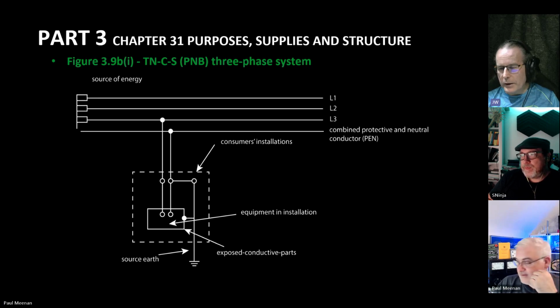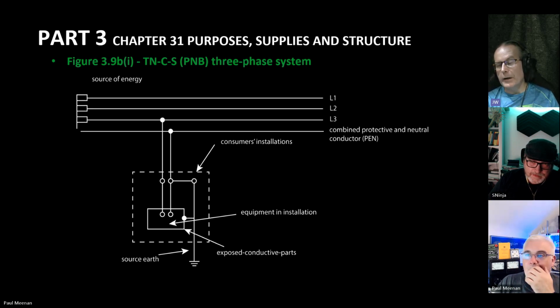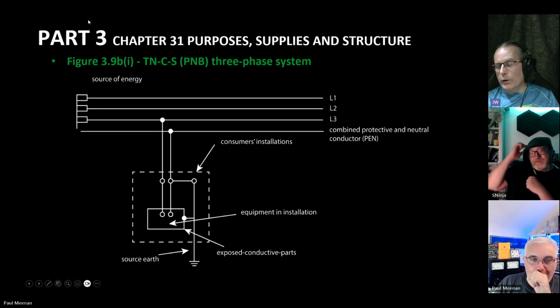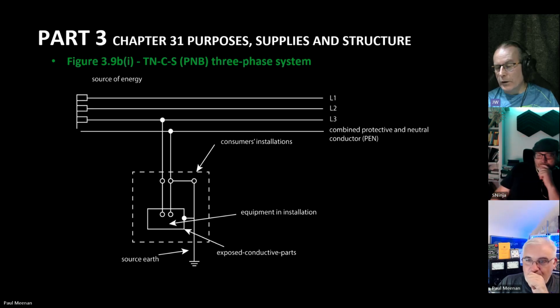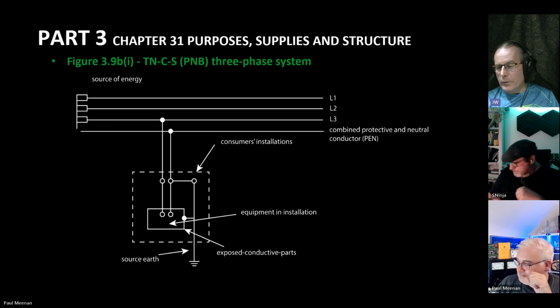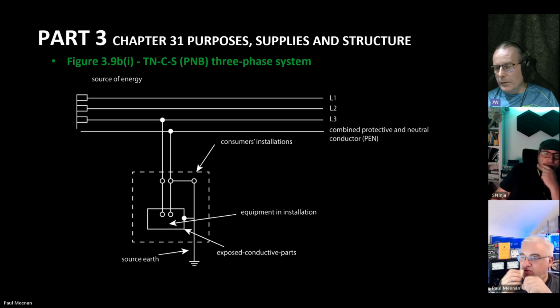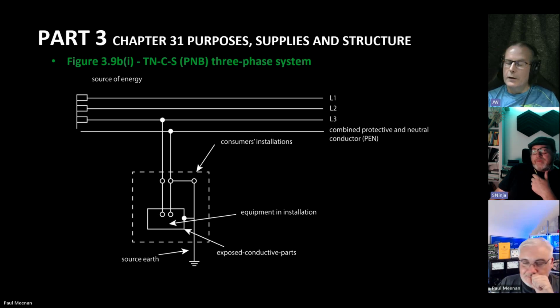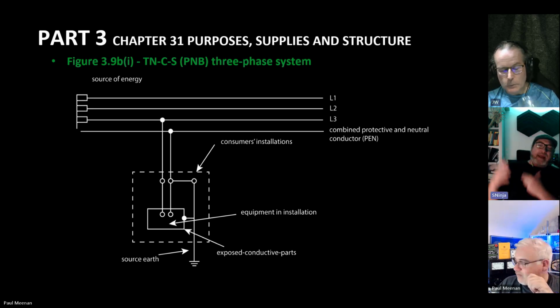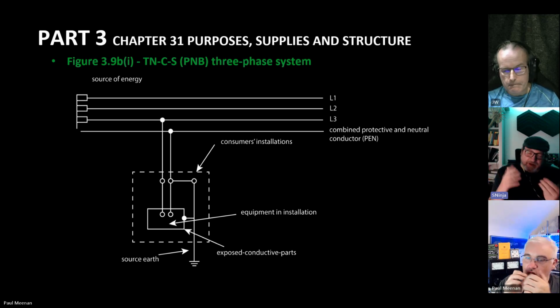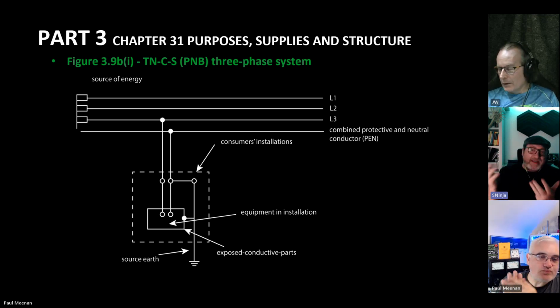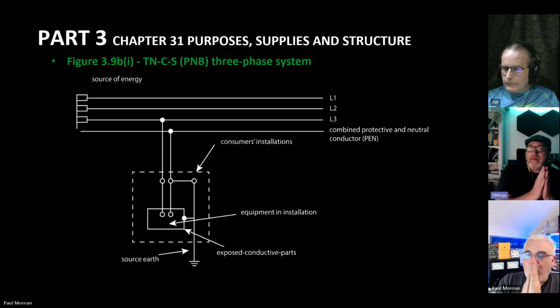The key difference with these on the diagram is that it's still TNCS. The difference between PNB and PME is that with PNB there's only one connection between the neutral and earth, and that's in the dotted box there, and that's also where the electrode is. Whereas with PME, you've got a link there, but there's also going to be other links in the actual network itself, and other electrodes in the network as well, which is where the multiple earthing bit comes from. So inherently, does that mean that the PME, with the additional multiple pathways through the earthing system to the neutral, is a more hazardous scenario than a single connection PNB?